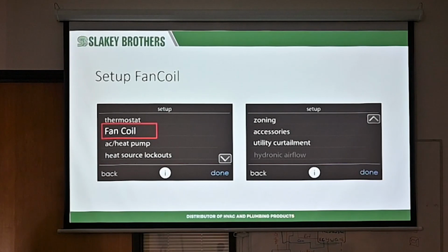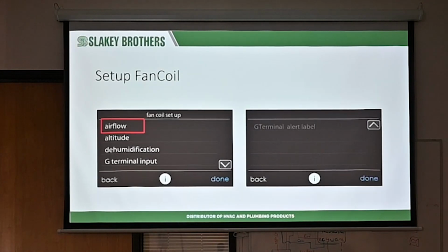Okay, now we're going to go into setting up the actual equipment itself. And we're going to start with the fan coil. When you set up a fan coil, it's going to give you these options here. Airflow, altitude, doesn't really have to do anything. Dehumidification, if you've got to do anything with it, there's a few set points. And then the special G terminal. We'll discuss that here in a second because it's a neat little feature you can do with that.